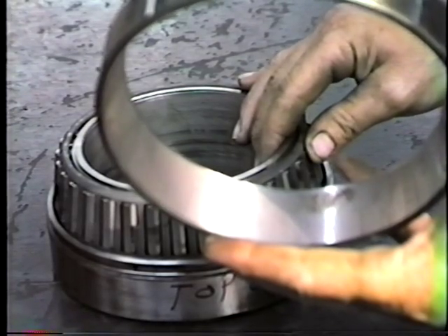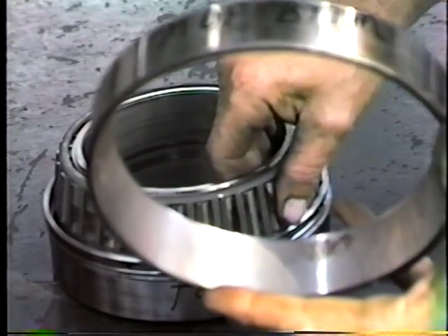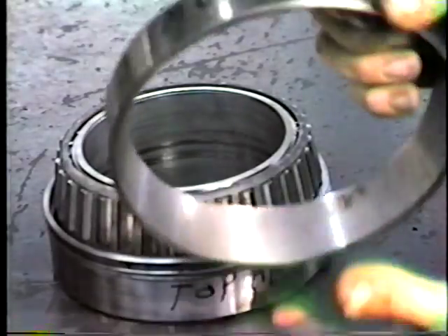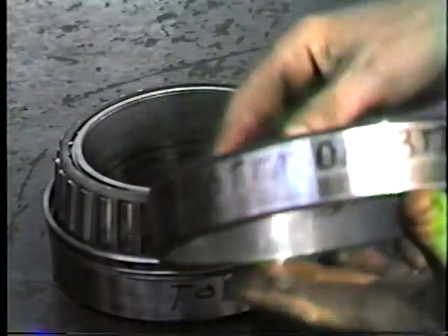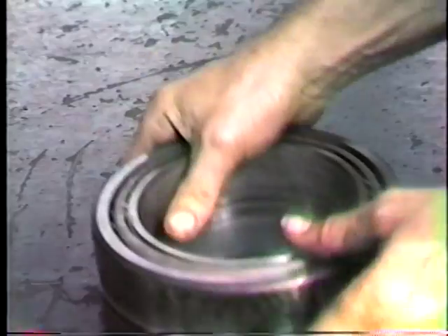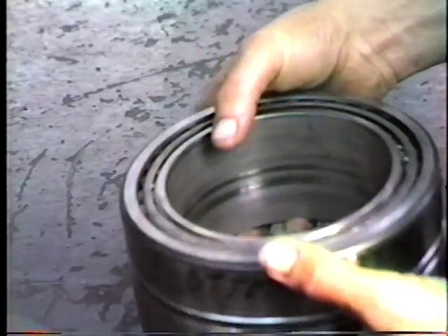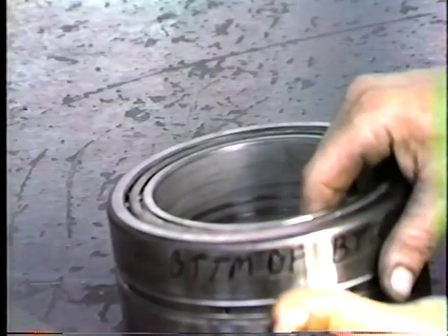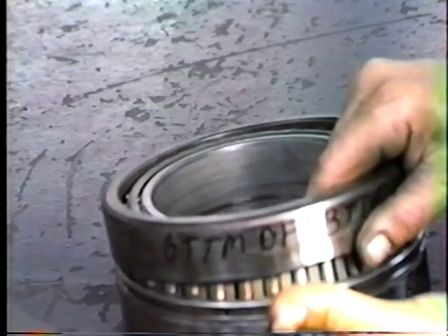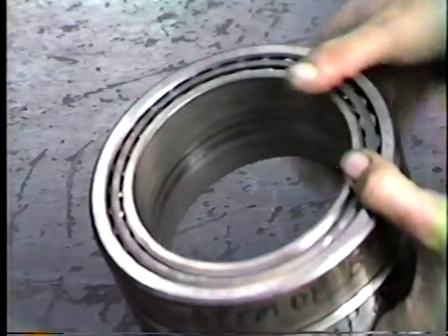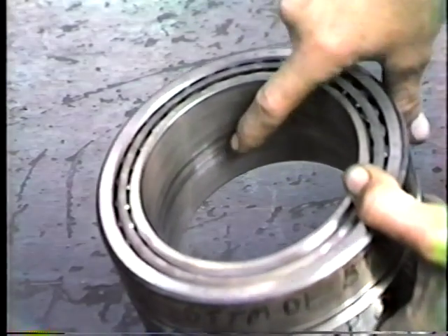That's good. Keep it going. Okay. This bearing, the only wear was as far as the movement on the clearance here. Point to those rings inside there, on the inboard. Looks like those things have been rolled on the inside. Yeah, it looks like it turned on the shaft, doesn't it?